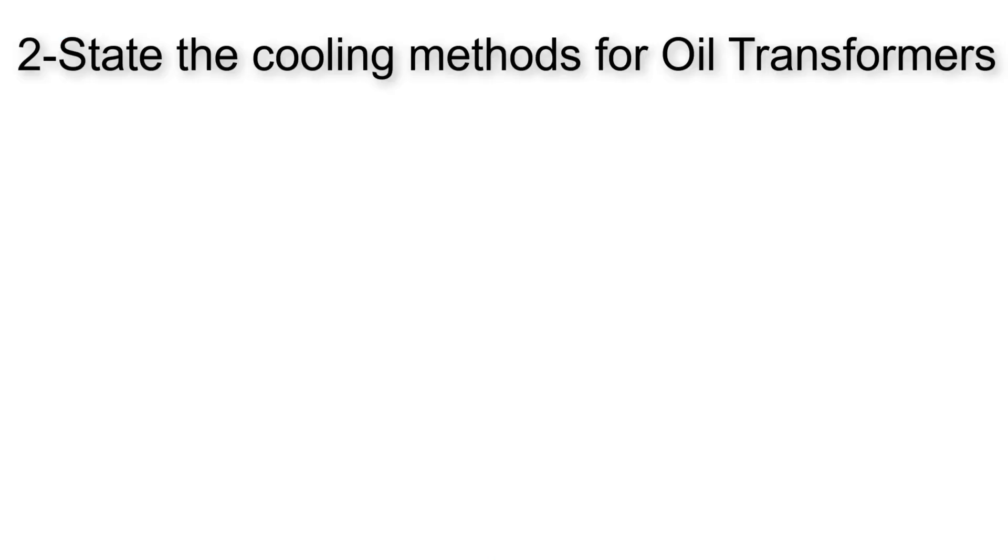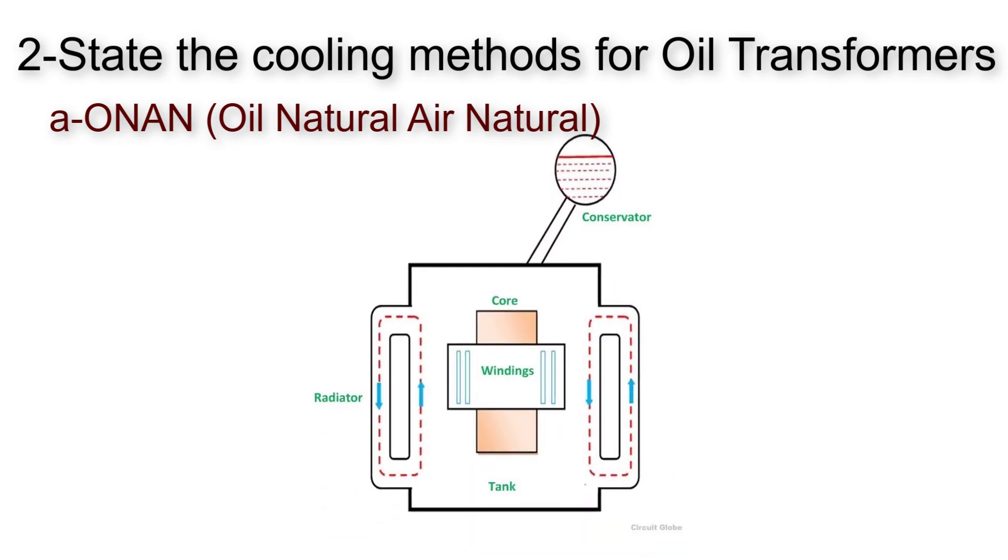The second question here is state the cooling methods used for oil transformers. Here we have ONAN, oil natural air natural. The oil moves naturally on the radiators and the air flows naturally through the radiators to cool down the oil without any interference.